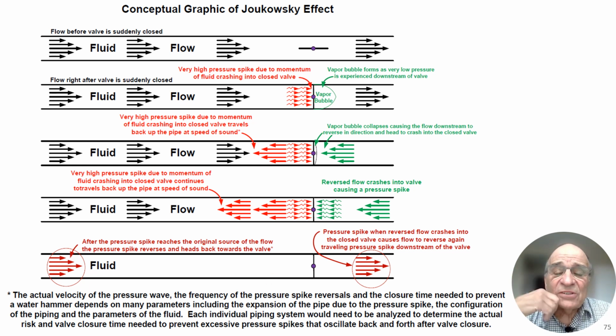Now also what happens on the downside of the valve is you have a vapor bubble form. And that vapor bubble starts to slow down this LNG that's downstream of the valve. And what does it do? It then starts heading back to the gate valve, and boom, it crashes into this, I said gate valve, a butterfly valve is what it was. And when it happens, you get that pressure spike that goes back again. It's a phenomenon that very few people are aware of.